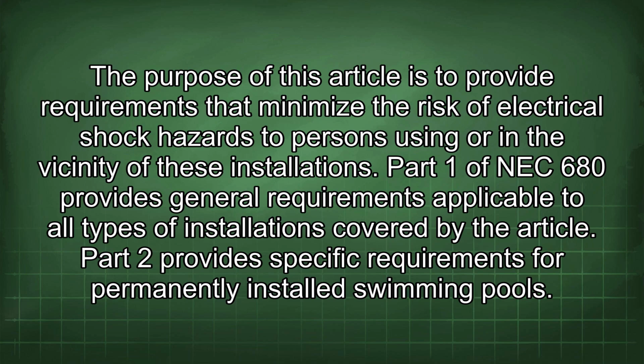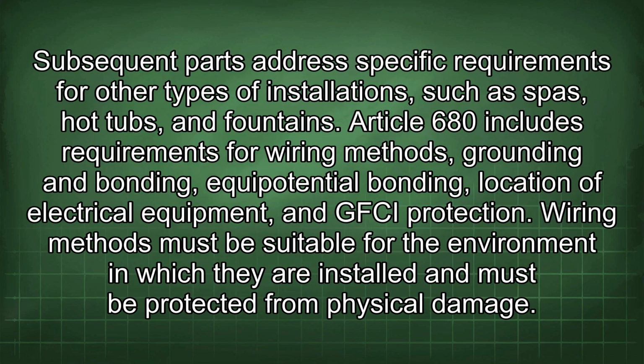Part 2 provides specific requirements for permanently installed swimming pools. Subsequent parts address specific requirements for other types of installations, such as spas, hot tubs, and fountains. Article 680 includes requirements for wiring methods, grounding and bonding, equipotential bonding, location of electrical equipment, and GFCI protection. Wiring methods must be suitable for the environment in which they are installed and must be protected from physical damage.